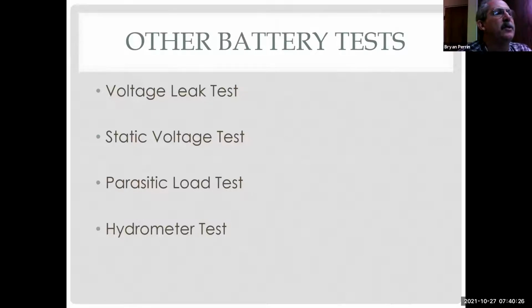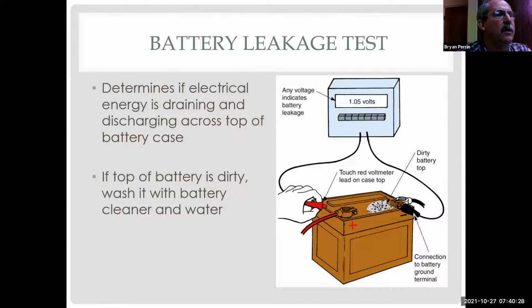A battery leakage test checks for battery acid leaking out of the case. The terminals are sealed and the case is plastic. However, if I have battery acid on top of the tray, it can allow an electrical connection to be made between positive and negative, or even between positive and ground. So I can check the voltage between the negative terminal and the battery case, or the positive terminal and the battery case. I can go either way, and realistically I should check both.